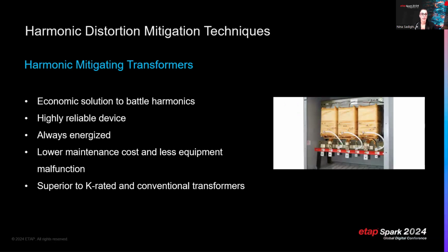Another harmonic mitigating technique is transformers. Mitigating transformers are low maintenance, low cost, and they are superior to K-rated transformers, and they do absorb harmonics. They always stay energized and they are reliable. But to be able to accurately determine the required technique, we have to perform an unbalanced harmonic analysis. And I will pass on the presentation to Jose from ETAP Dynamics Department to explain how.